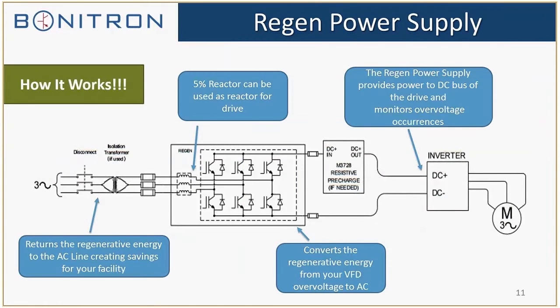The regen power supply provides power to the DC bus of the drive and monitors the overvoltage occurrences. Just like before, it's going to convert the regenerative energy from your VFD back to the AC line. But you will see a big difference in the wiring configuration from the regen to the regen power supply — you don't have the AC side hooked up to the drive. There's no need for that when you're using the power supply. That takes out some hardware for integrators that is no longer necessary when they're using our regen power supply.